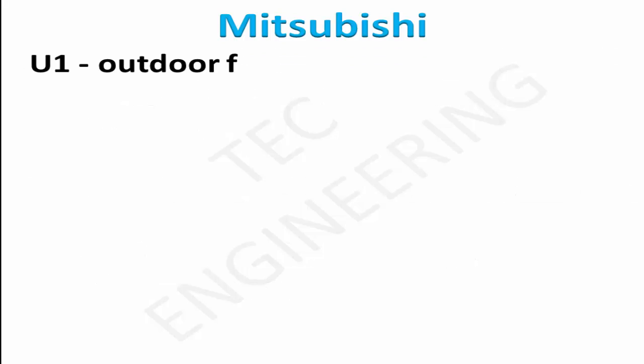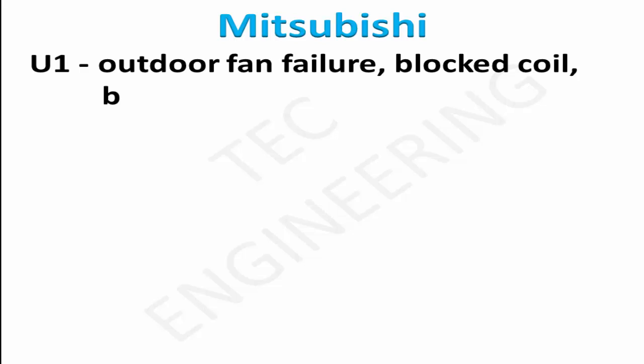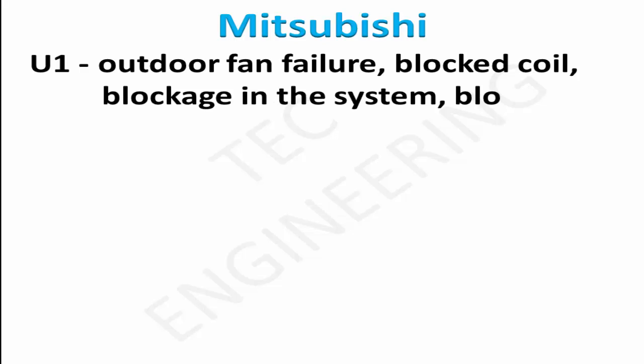U1: outdoor fan failure — blocked coil or blockage in the system. Also check for blocked filters on indoor unit in heating mode. U2: outdoor unit fault.